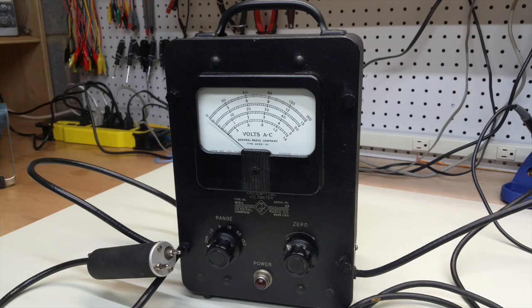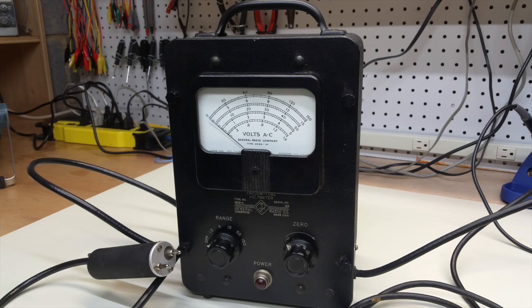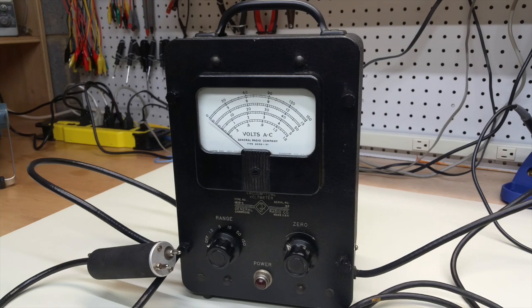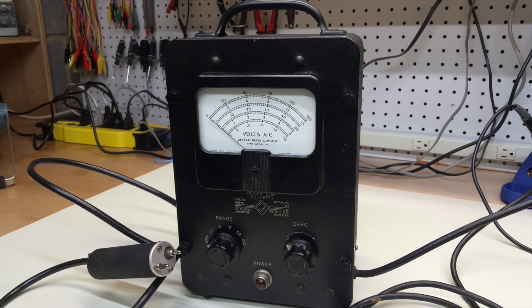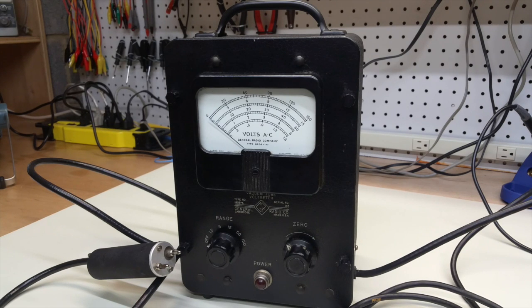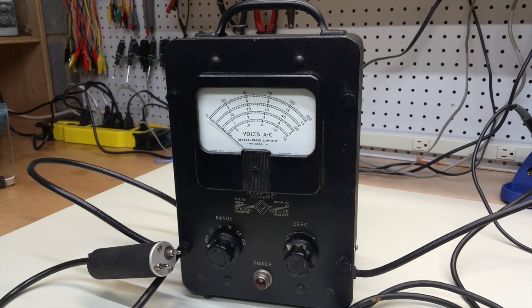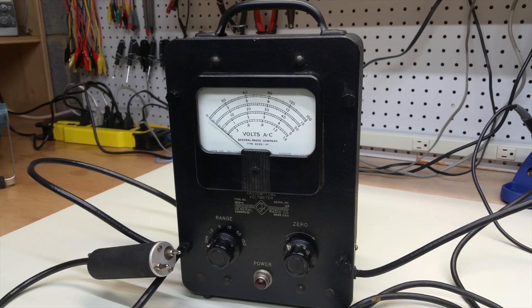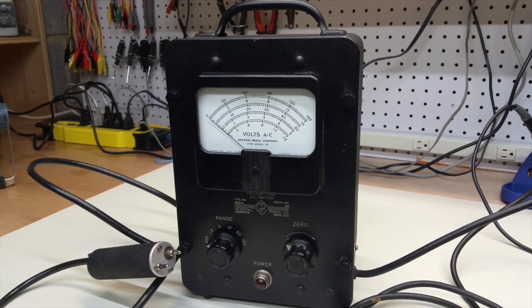It does this through an active probe that includes inside the probe a vacuum tube diode. What we're going to do in this video is we're going to open the unit up and check it out, check the resistors and capacitors, make any replacements that need to be made. We'll test the tubes and examine the cords and make any necessary repairs there. And then we'll test the unit out and see if we can bring it into calibration.